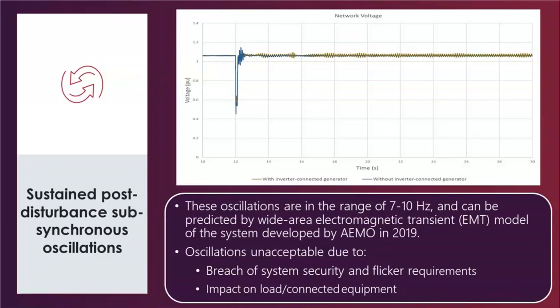This graph shows a typical example that we have been seeing in different regions that we operate over the past 12 to 18 months, whereby we see sustained low frequency post-fault oscillations caused by inverter-based resources that wouldn't otherwise be present in the power system. These oscillations, typically between 7 to 10 hertz, have been predicted very accurately by the wide area EMT model of the power system that we developed internally last year. These oscillations are not acceptable, firstly because they breach the system security and flicker requirements, and secondly because of the potential adverse impact on some loads or customers that require a level of purity of supply.